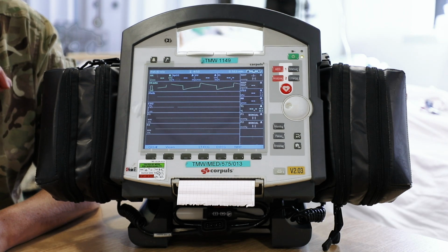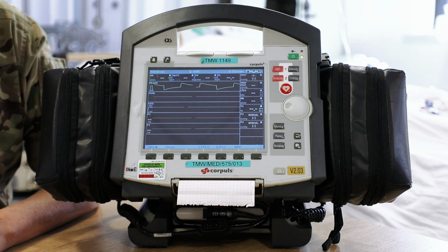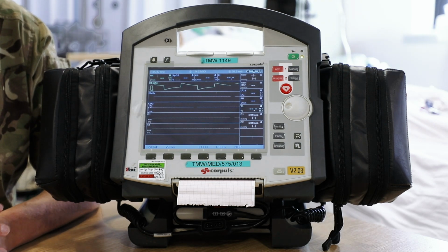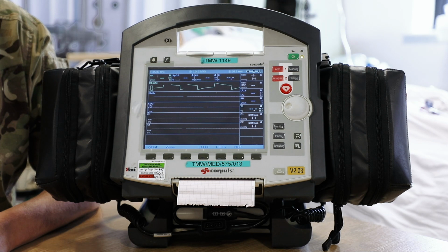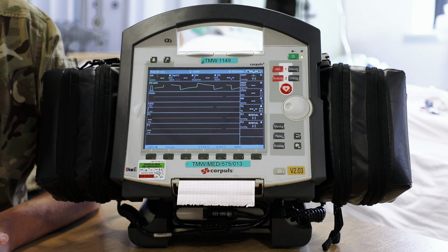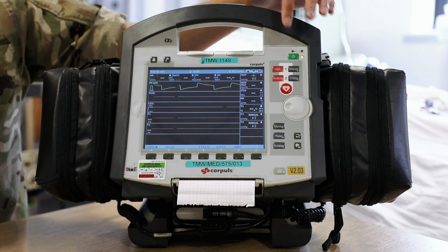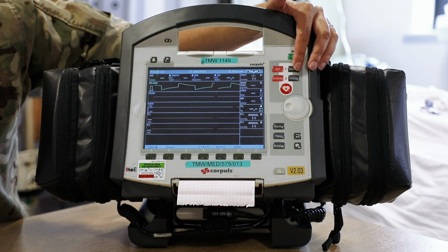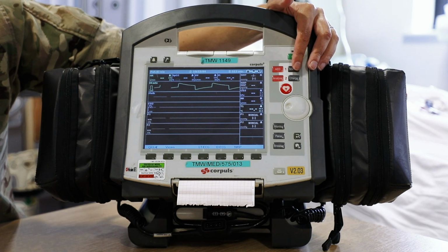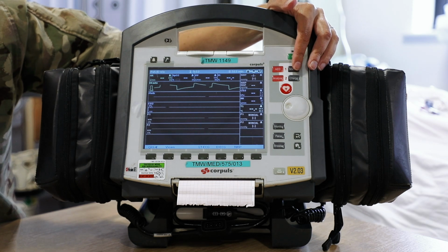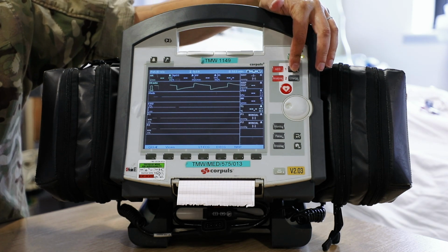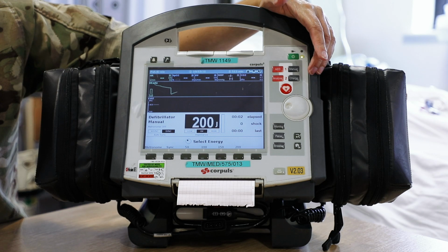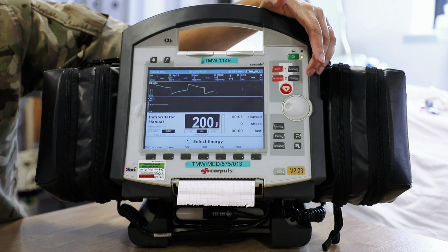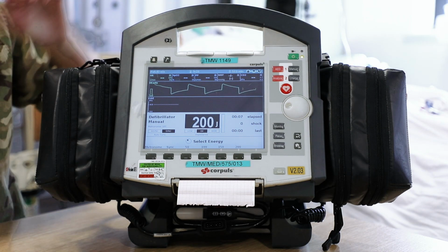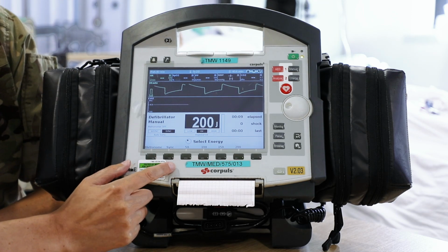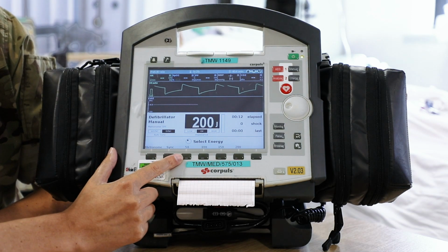We already confirmed that our white diagnostic ECG plug is already unplugged because I didn't plug it back in after our checks. The first part of the check is using the manual function here. Is we're going to confirm that we can charge up the defibrillator and that we can also disarm it. So if we press the defib button, you'll notice that the defib function comes up at the base of the screen. And first things first, it's worth just confirming that all the soft keys function correctly.